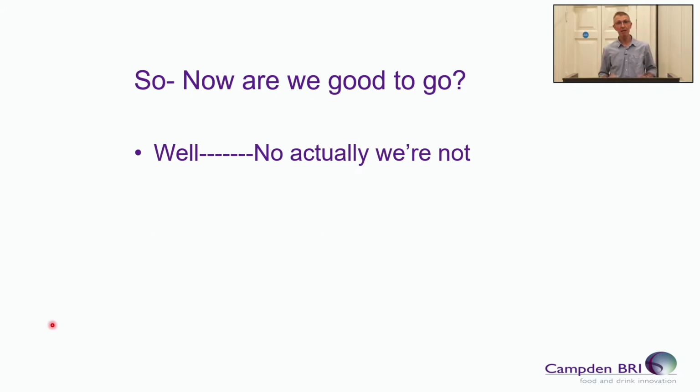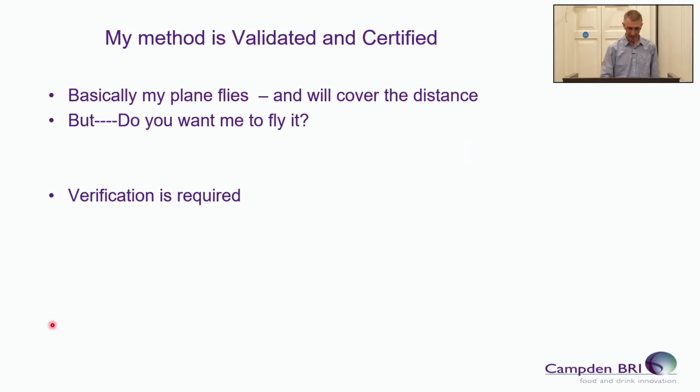So, does that mean we're now good to go? Are we okay now to go and use that method? Well, no, actually we're not. Because the method's been validated and it's been certified. So basically, in my simple terms, my plane flies and it covers the distance, but would you want me to fly it? Verification is now required. And this is where individual laboratories come in. Every lab has to verify that the method that they've picked can be used in their laboratory and get the correct results.